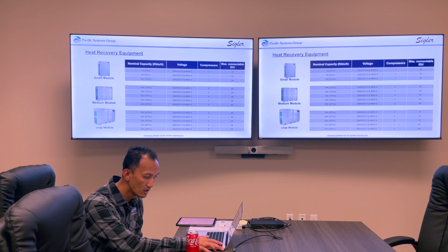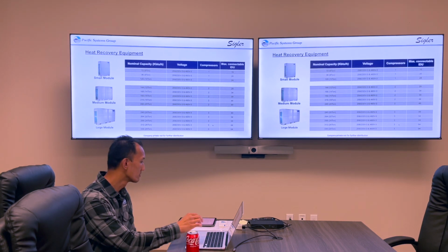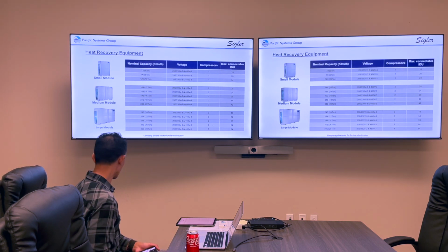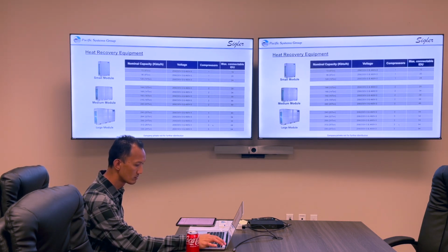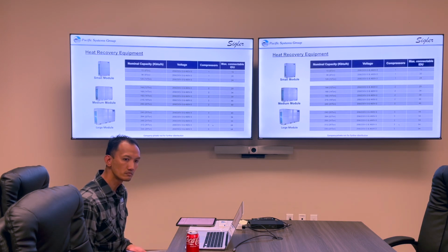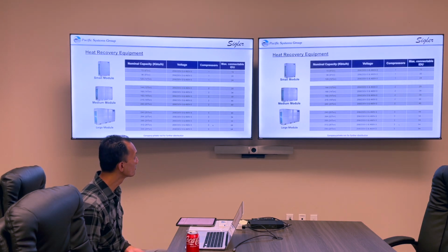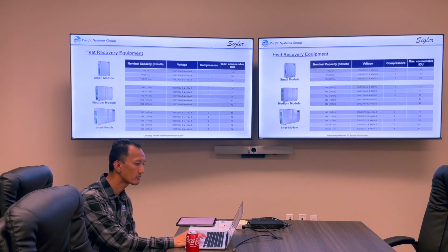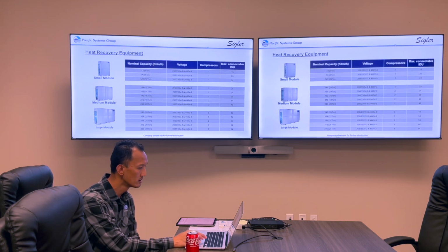Sizing off the system, we have multiple indoor test sets, looking at the lowest load scenario. It'd be nice if we have this chart right here with a turn down percentage, so that we can make sure that the particular unit we're selecting is going to be able to turn down to the lowest load that we have on the zone or out of the zones that we're connecting it to. Yeah, I'll look into that and get back to you and get you a hard number if there's a hard percentage that we published. Okay, great, thank you.